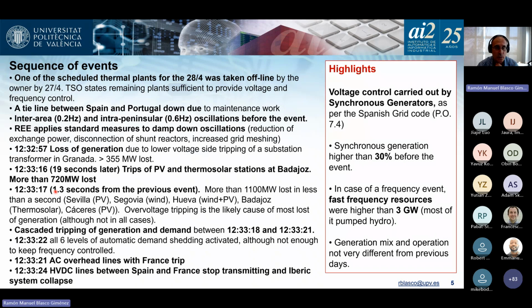1.3 seconds after, there were cascaded trips in the south and central Spain. We're talking more than 1.1 gigawatts. And that was followed by cascaded tripping of generation and demand in the following 3 seconds. Load shedding was not fast enough, but it operated correctly when it reached the low frequency levels. At 12:33:21, the AC overhead lines with France tripped, and 3 seconds afterwards, the HVDC lines stopped transmitting between Spain and France, and the Iberian system collapsed.